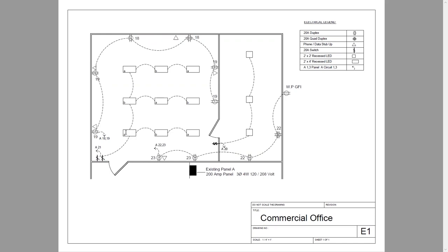When you really run the conduit, you have to go up out of the wall, across, and even down into light fixtures. Rather than running from fixture to fixture at the same level, you'll come out of the top of a fixture a little bit, go over and down into the top of another fixture. Same with outlet feeds. We're going to do the takeoff for MC cable.